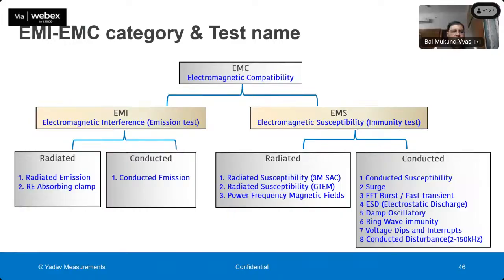Electromagnetic compatibility means electromagnetic interference testing, and the other is electromagnetic susceptibility testing, which is also called immunity testing. The electromagnetic field, or the RF field, can travel through cables, which is called conducted, and it can travel through air or vacuum, which is called radiated. So all these electromagnetic interferences are tested in two conditions: one is radiated, the other is conducted. Similarly, immunity is also tested in radiated and conducted mode.